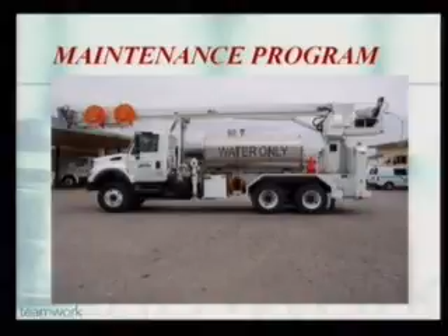The other program that we have is what we call the Transformer Information Load Management Program. On a quarterly basis we look at all our transformers on poles and inside the vaults, and look at how they're loaded. And every spring, about this time, we look at the replacement program, looking at the worst case condition based on what the predicted peak will be for the summer. We use this program on a feeder by feeder basis, distribute the load, estimate how the transformers would be loaded, and do a replacement.